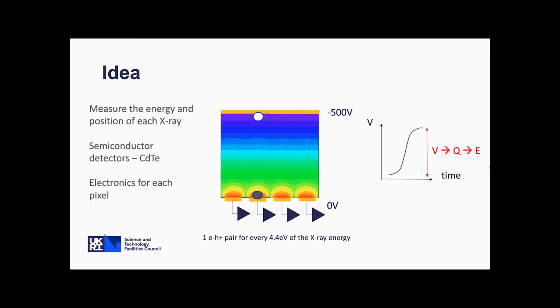And that charge cloud then drifts under the electric field. And as it drifts, it diffuses and expands due to electrostatic repulsion. Then when it gets close to the pixel, it induces a signal on that pixel. And that signal is induced due to the small pixel effect or the Shockley-Ramo theorem, and that gives us this voltage pulse on our electronics. That voltage pulse is proportional to the charge which was deposited by the X-ray, and in turn that gives us the energy of the X-ray.